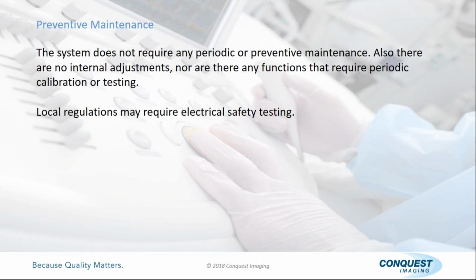Now, there are different limits for leakage for each type of probe, body floating, cavity floating, all that. But just from my personal experience, if it's over 10 microamps, it needs to be taken out of service, because probes are designed not to leak. Okay? They're not supposed to leak. You should have 0 to 2 microamps or so. You stick it in there.